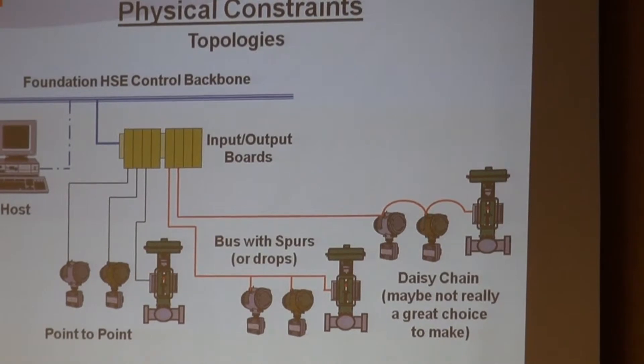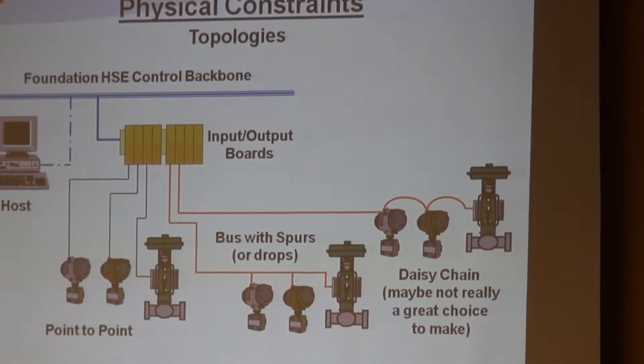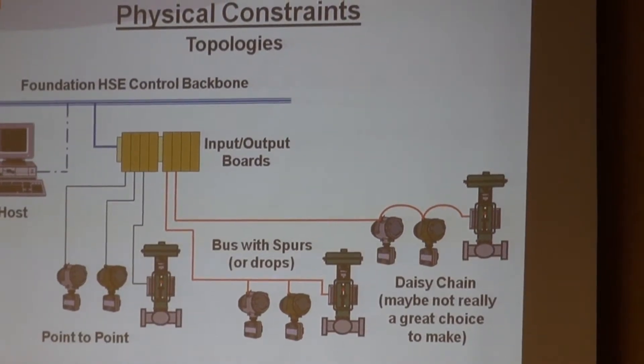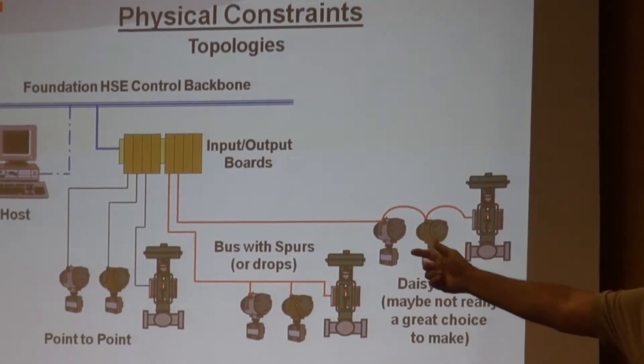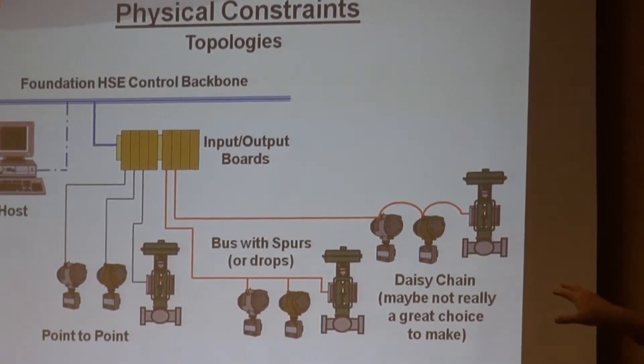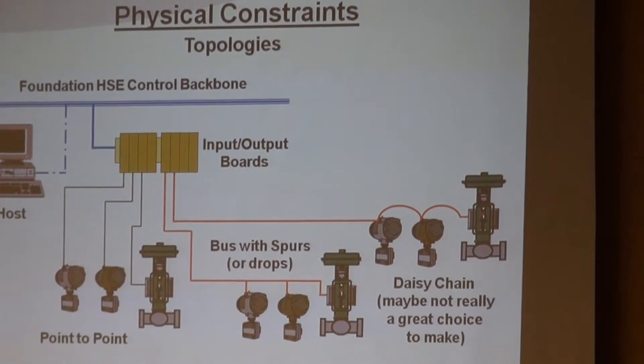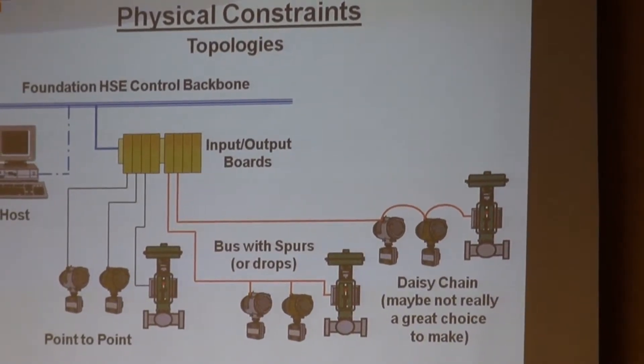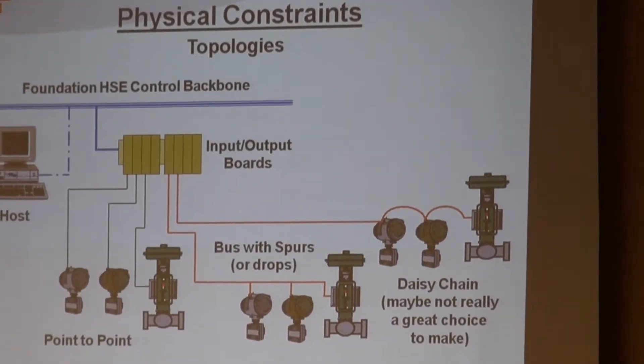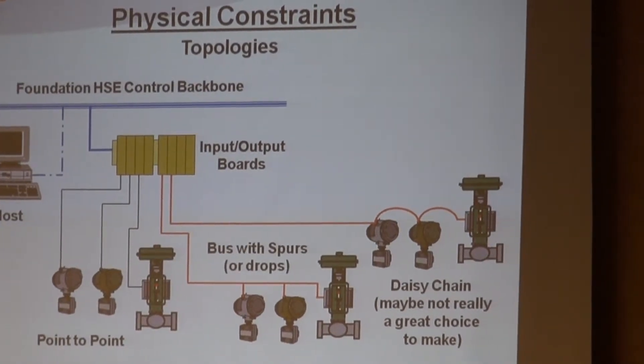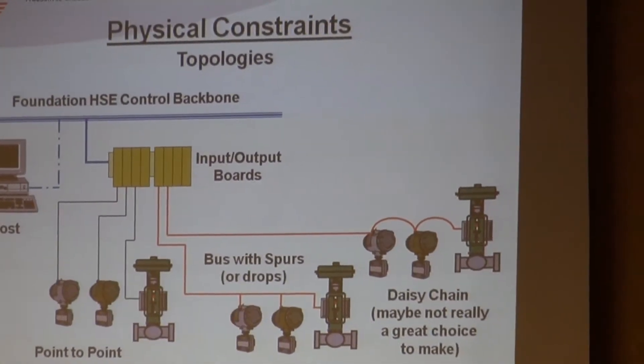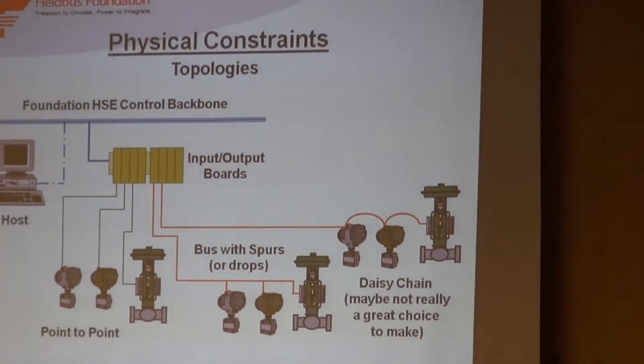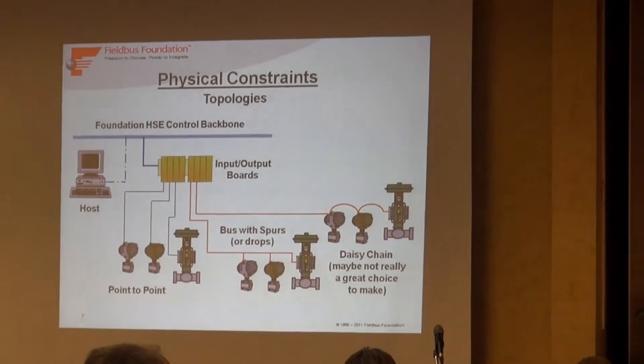Bus with spurs is another variation where you run a trunk out to the field and do drops - here's a device, here's another, here's another. A variation of that would be what's called trunk-in, trunk-out. You can have multiple device couplers on that same trunk. Just make sure that your terminator is on the very last one. So you can have lots of variations of this bus with spurs.